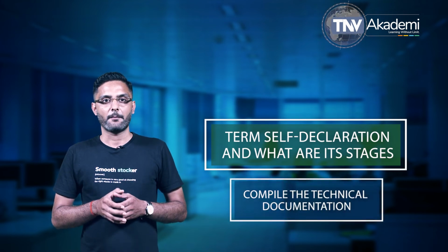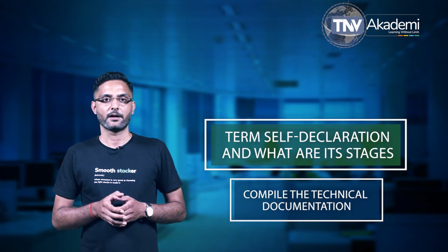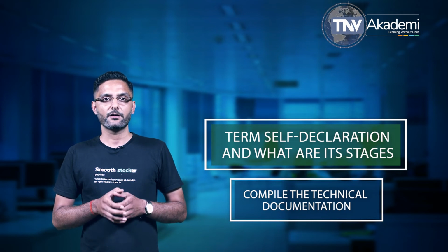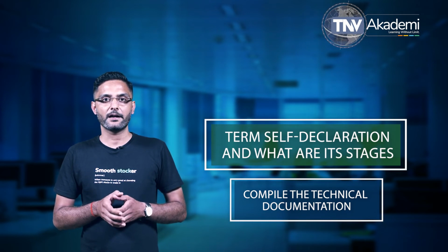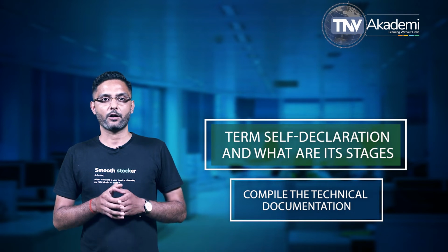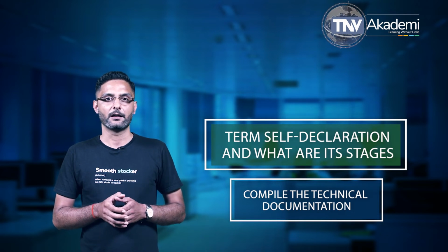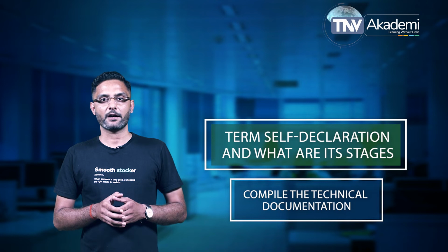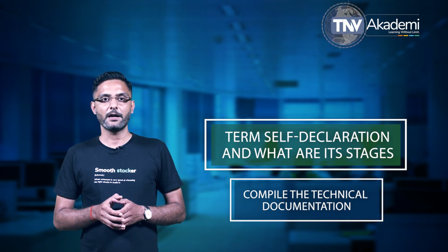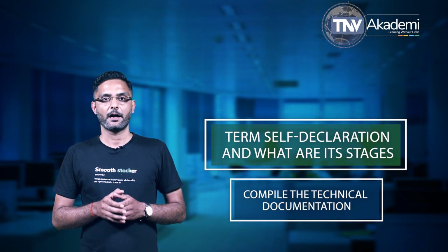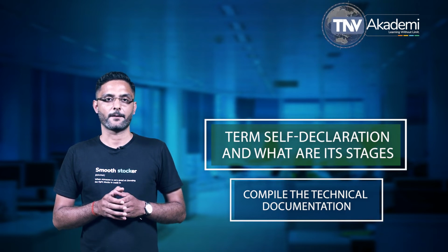Stage 5. Compile the technical documentation. It means technical documentation, usually referred to as the technical file relating to the product or range of products, needs to be compiled. This information should cover every aspect relating to conformity and is likely to include details of the design, development, and manufacture of the product.